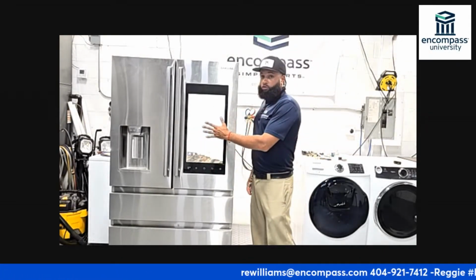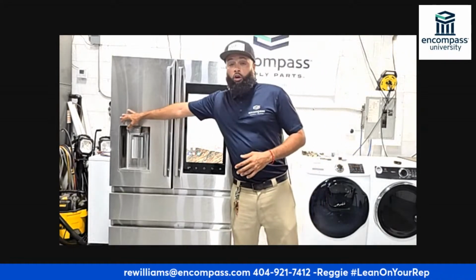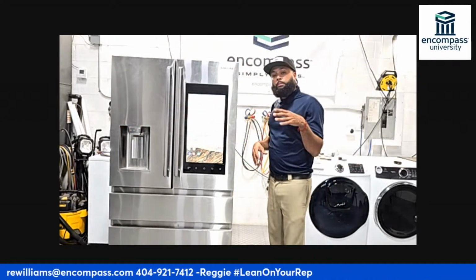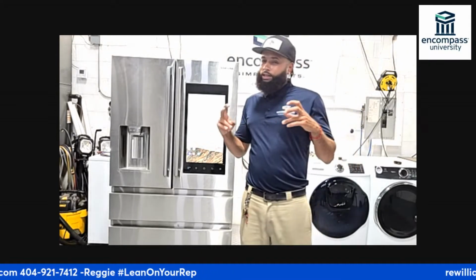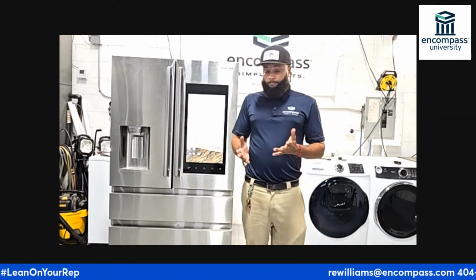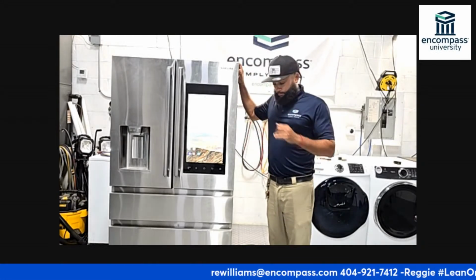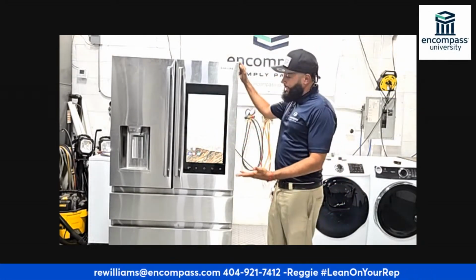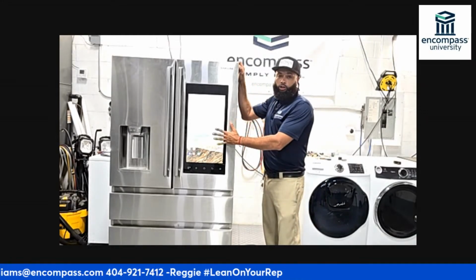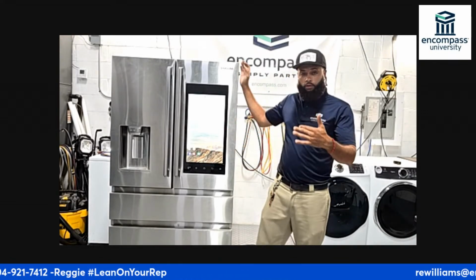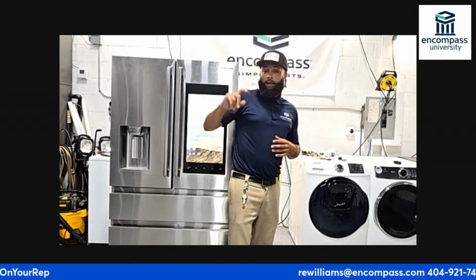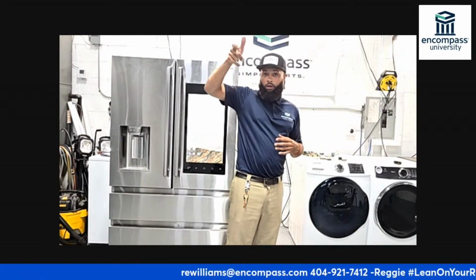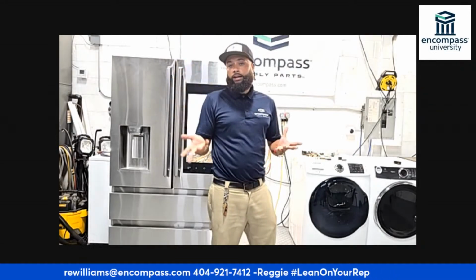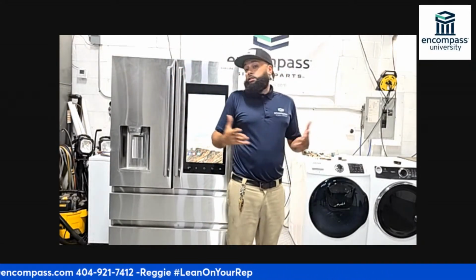That can be entered through this display, or on older models with older displays, you can place the unit into showroom or demo mode. What happens is you get to the customer's house, the customer says the fridge isn't working, but the lights are on. Always verify that your controls are in proper operation. Even going back to old analog refrigerators with dials, always make sure your controls are in the right setting. It's happened to me that the fridge was just off, and the repair was to turn it on. So always make sure your controls are good.